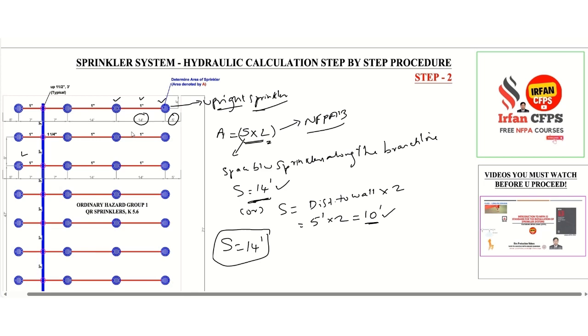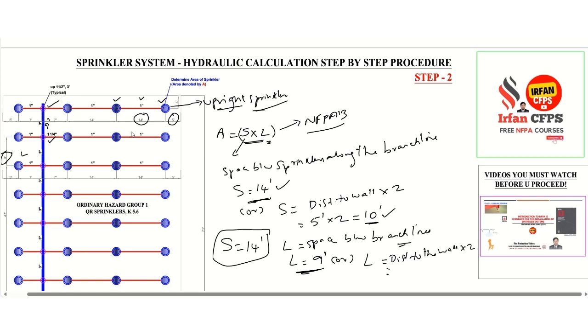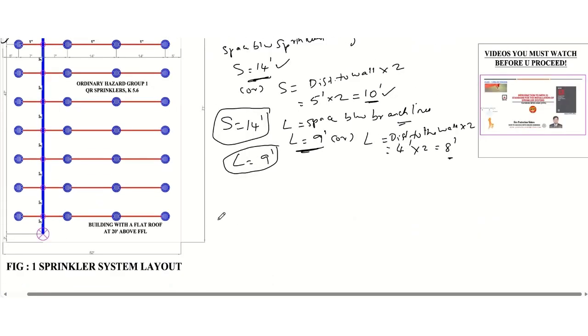L is the spacing between branch lines. Here we have one branch line and another, and the space between them is 9 feet, so L could be 9 feet. Alternatively, L equals distance to the wall times two: the distance to the wall for this sprinkler is 4 feet, so 4 times 2 gives 8 feet. The largest of these two is 9 feet, so L equals 9 feet.